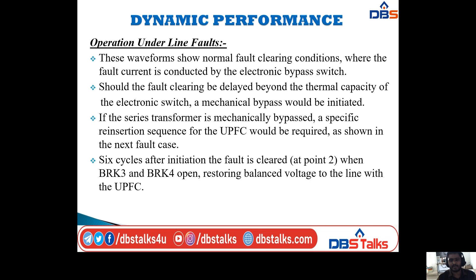Next, line conditions quickly return to normal, and the UPFC responds by removing the electronic bypass and immediately returning to the pre-fault power flow control mode, that is at point 3. Breaker 3 and breaker 4 reclose with no noticeable effect, that is at point 4.